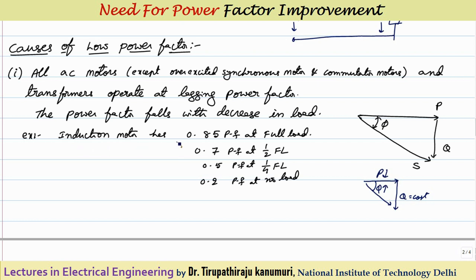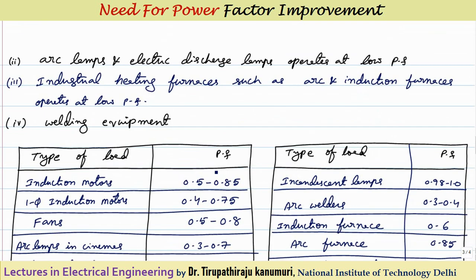That is why an induction motor under full load operates at nearly 0.85 power factor. At half load, reactive power is still nearly constant but active power is halved, so the power factor decreases further. At one-quarter load it may be around 0.5, and under no load the power factor may drop as low as 0.2. Similarly, arc lamps and electric discharge lamps used in street lighting, as well as industrial heating furnaces such as arc and induction furnaces, and electric welding equipment — which are essentially welding transformers — all operate at low power factor.